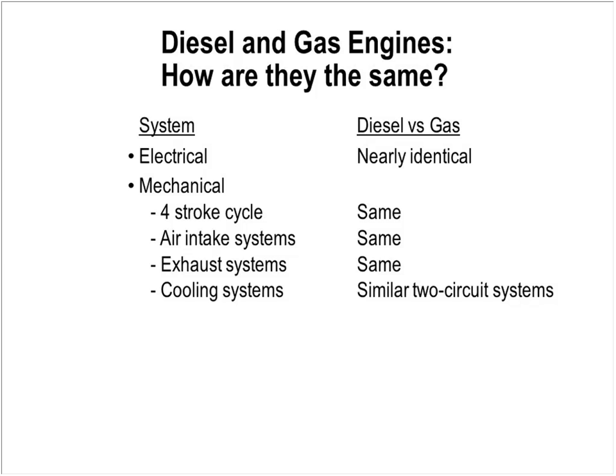In terms of exhaust systems, it's very similar in nature. The designs in terms of sound attenuation—if I require a stainless steel skin on the muffler in a diesel engine application, I would require probably the same for the same reasons in a gas application. Again, restrictions become part of that issue. As I have restrictions limiting the length of my runs and number of bends I can have, and how I install those runs, you'll have similar situations between gas and diesel.